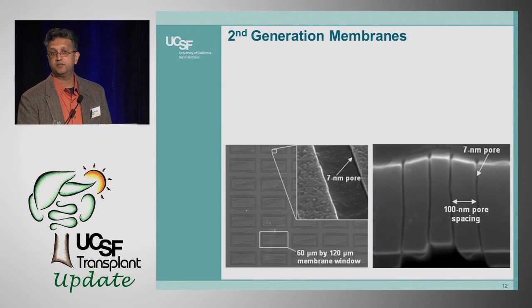Before, I talked to you about 10 milliliters per minute, that's 600 milliliters per hour. And we can actually run this off perfusion pressure, so it's 30 or 40 millimeters of mercury. We should be able to get 30 milliliters of clearance. So that's the thinking behind how we need to get to these numbers, by sticking to a technology that's manufacturable. That's really important because many times we come up with new medical devices in the lab that languish because there's no way to manufacture them beyond the lab. But by picking the technology that's available in Silicon Valley, we have a way to expand on that.